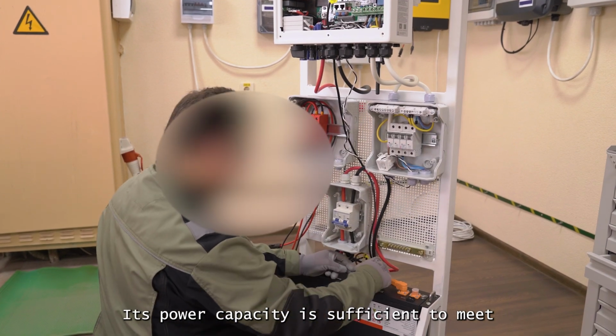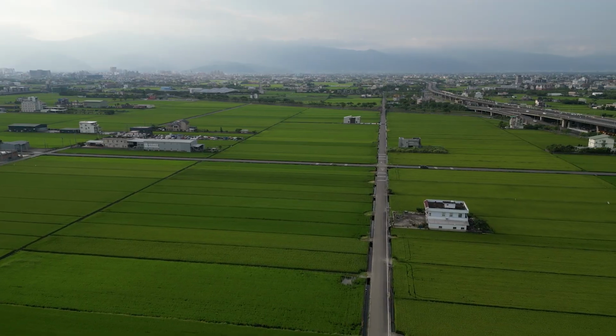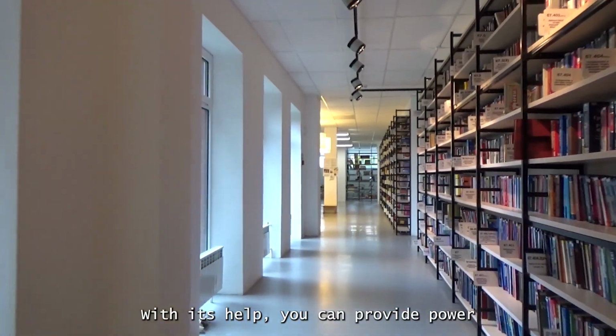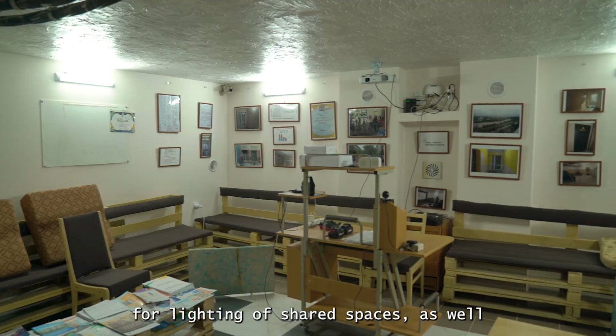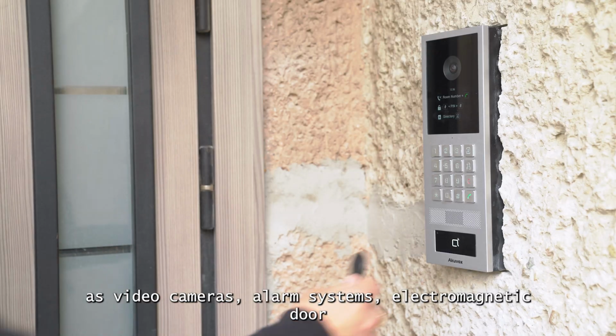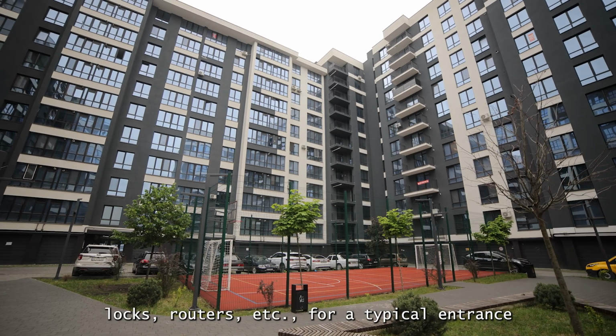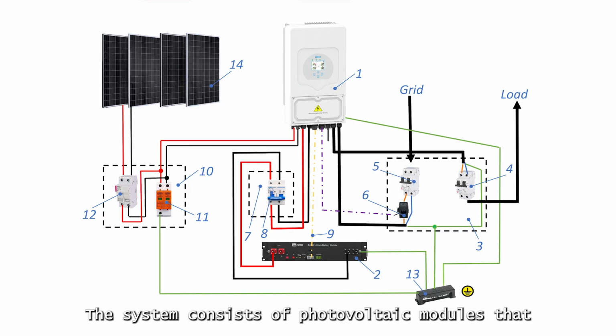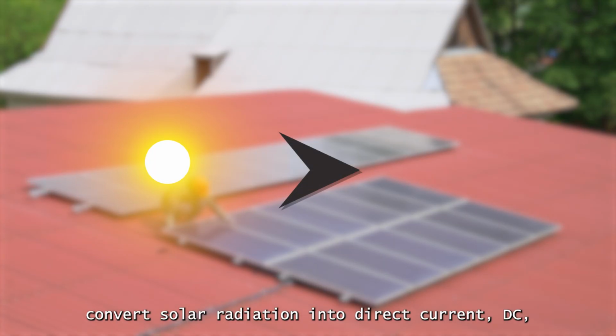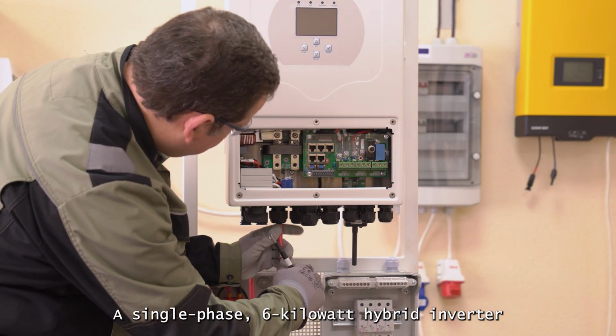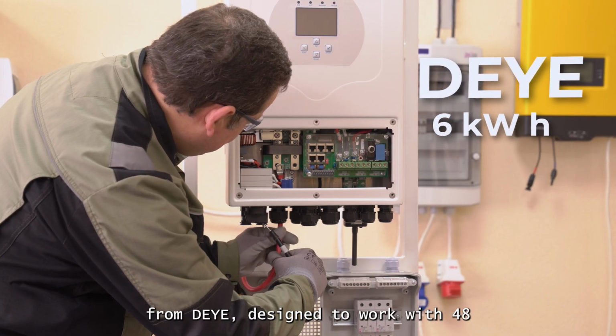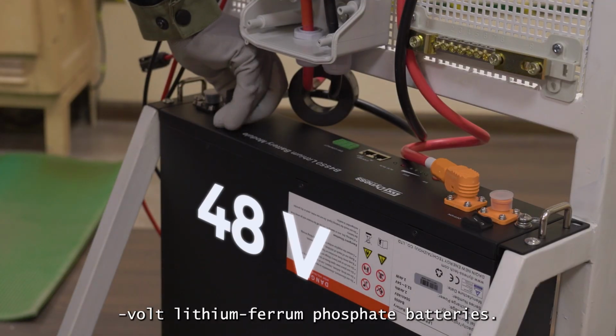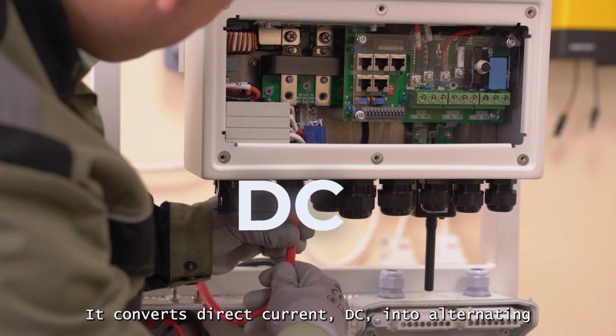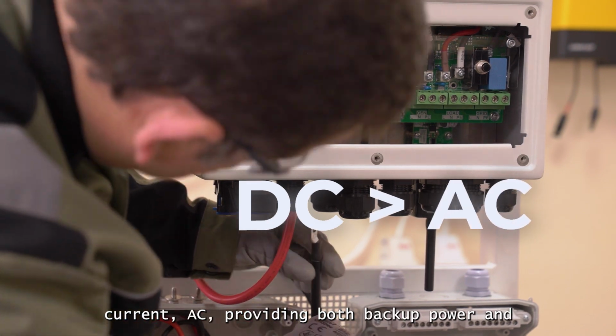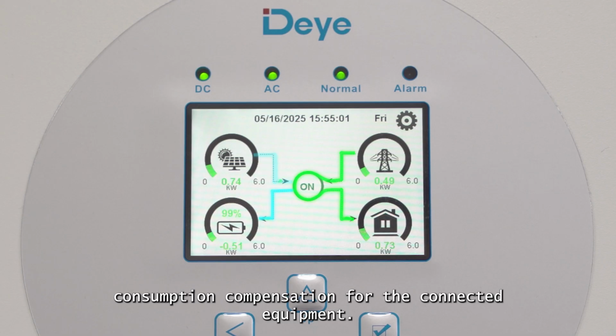Its power capacity is sufficient to meet the energy needs of HOAs, municipal institutions, or public organizations. With its help, you can provide power for lighting of shared spaces, as well as video cameras, alarm systems, electromagnetic door locks, routers, etc., for a typical entrance of a 9 to 10-story building. The system consists of photovoltaic modules that convert solar radiation into direct current, DC, electrical energy. A single-phase 6-kilowatt hybrid inverter from Deye, designed to work with 48-volt lithium iron phosphate batteries. It converts direct current, DC, into alternating current, AC, providing both backup power and consumption compensation for the connected equipment.